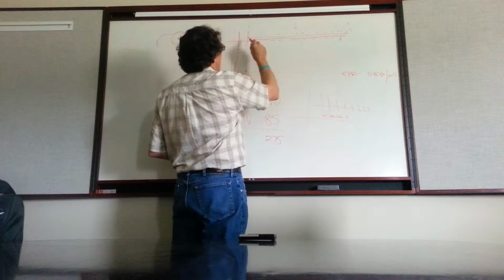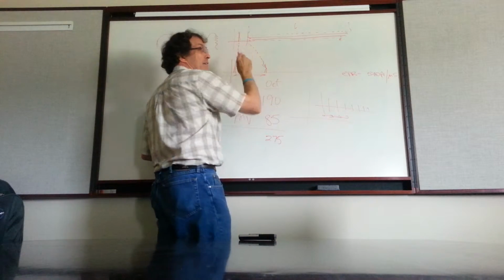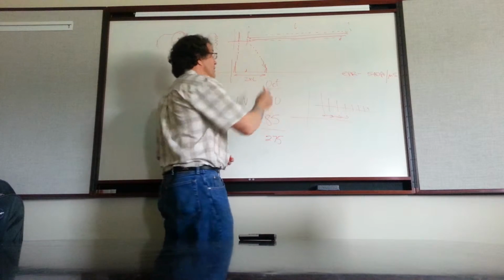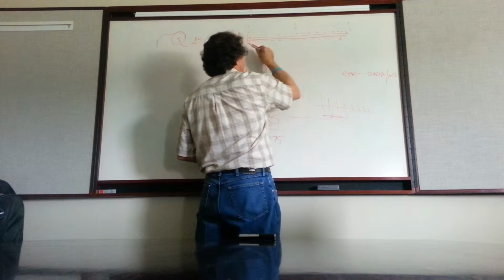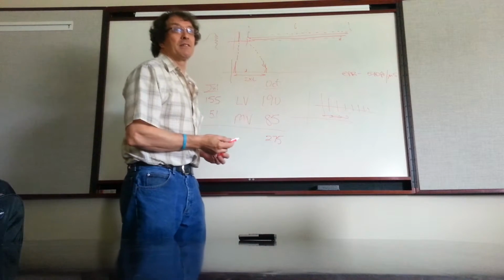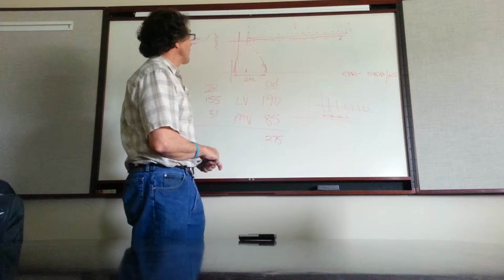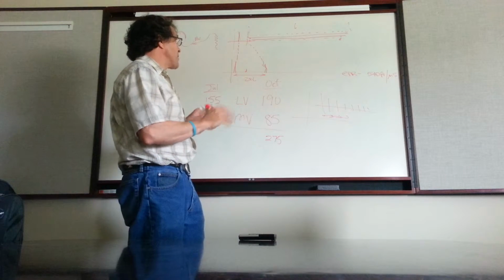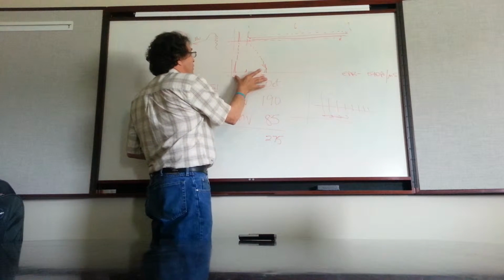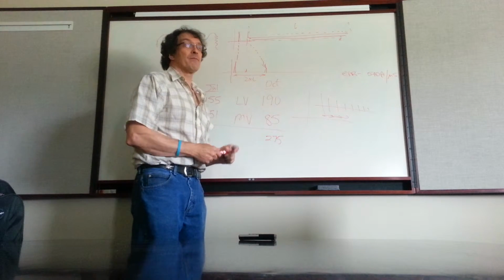Because when that pulse travels up here and comes back down again, when it hits this end, it's a discontinuity. So it reflects up here again, and then again, and again, and again. And it'll keep going until it's attenuated so small you can't see it. So it just keeps multiplying down the cable. So that's really the simplistic point of view. You're going to have 2 pulses here, and you're looking for something that belongs to the fault.